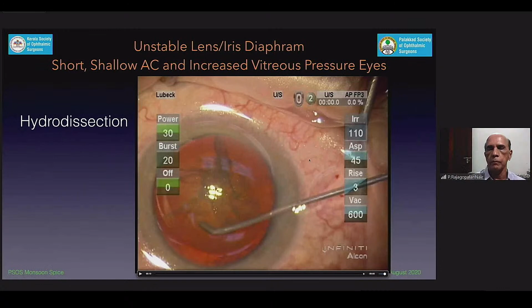ending overpressurization. For the phacoemulsification and I/A, once again, fluidically, we want a snug sleeve to incision size. Place a small amount of subincisional viscoelastic prior to entry. Enter the anterior chamber in foot position 0 with these cases. Lower the IOP to 28 to 40. Have a high IOP ramp. Protect the posterior capsule with the second instrument. And now or soon, we'll be able to use a hybrid polymer phaco tip, which I will use in high-risk cases. For I/A, again, a polymer or silicone-tipped tip is helpful.